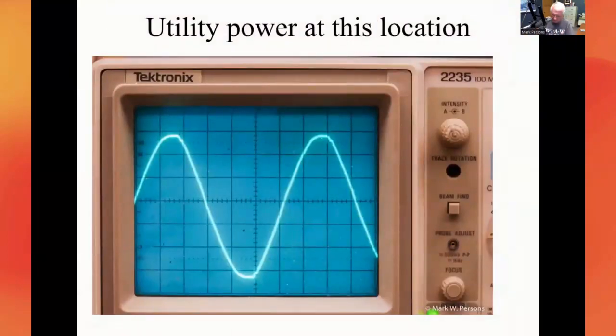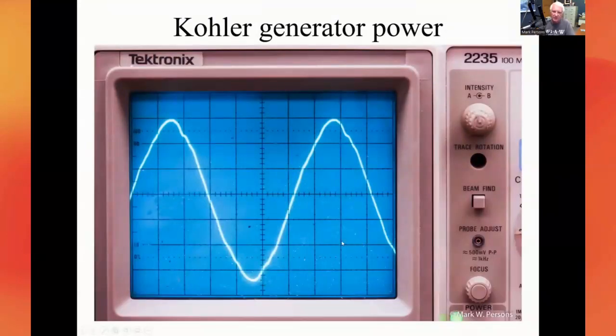Here is what utility power looks like here. There's about 2% harmonic distortion. That means that 98% of the waveform is a pure 60 hertz waveform, but 2% of junk is added. What we don't have is a nice peak at both ends of the sine wave, and there's some extra jitter in there. Anyway, that would be normal power today. This is what the Kohler looks like. It's able to overcome that peak shaving thing because it's doing real active voltage control.